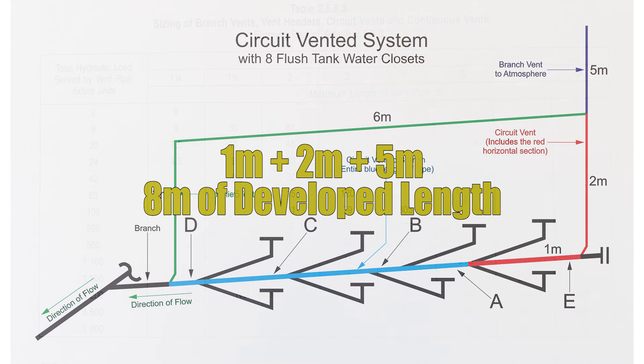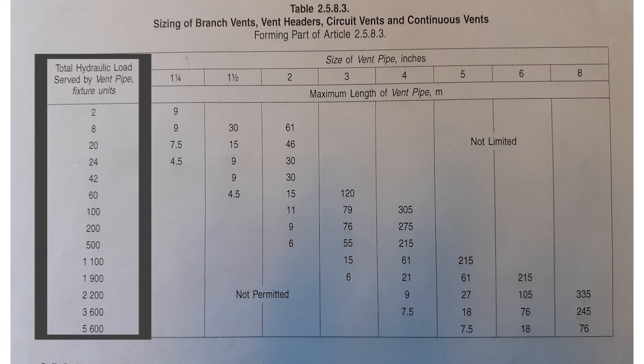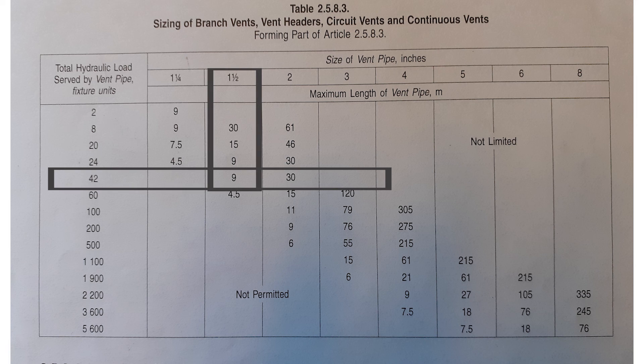Now we need to look at table 2-5-8-3. I go down the hydraulic load column on the far left — I have 32 fixture units, so between 24 and 42 I have to go to 42. Going across to the right, there's a blank space on the 1-and-a-quarter-inch column, but I can go up to 9 meters on 1-and-a-half-inch. Since I only have 8 meters of developed length, 1-and-a-half inches is good.